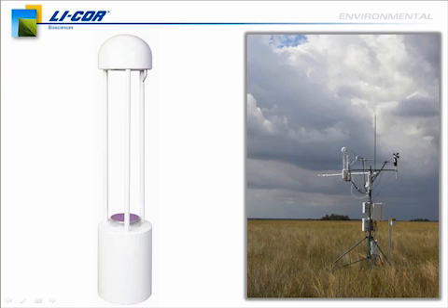The 7700 has self-cleaning optics, and it has temperature-controlled mirrors, so we provide more complete data sets in difficult environments where maybe in the past instrumentation would have had a hard time collecting data continuously. We've made several advances with the 7700 that make it more robust in difficult environments. And we really designed this instrument so it could be deployed nearly anywhere and then left unattended for data collection for long periods.